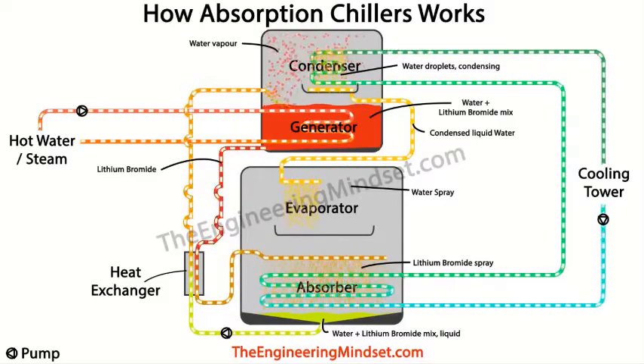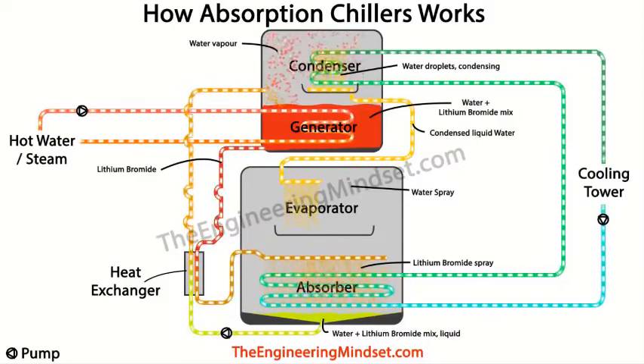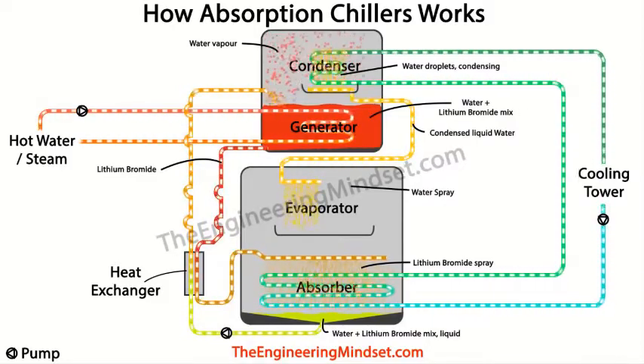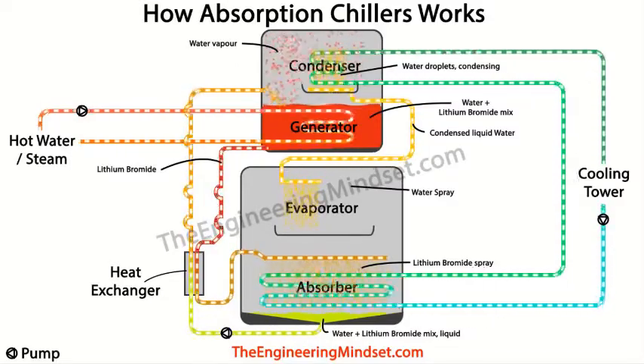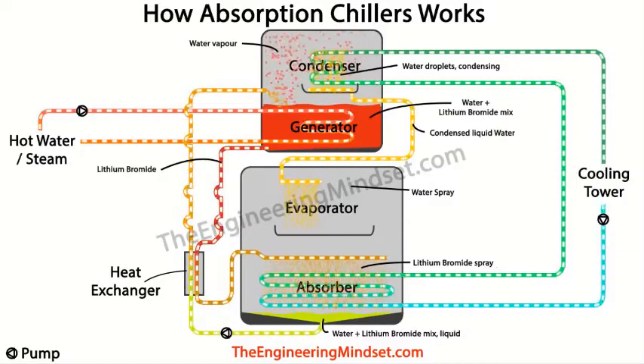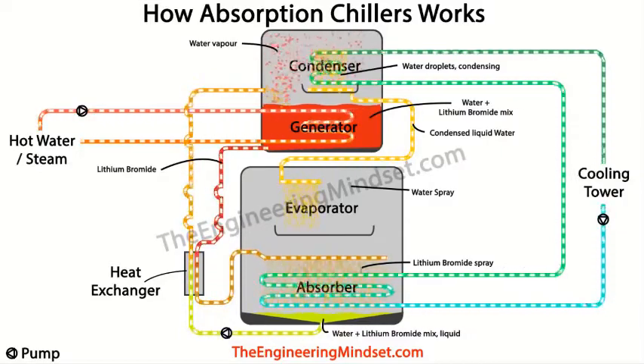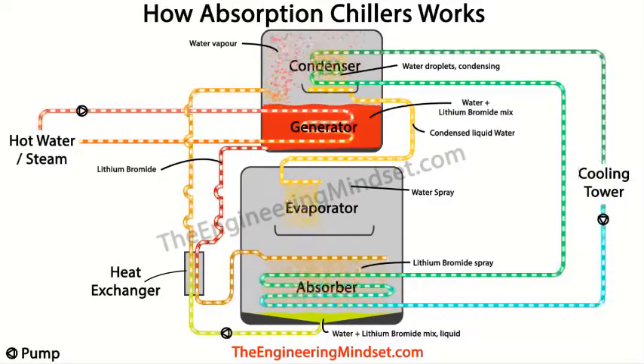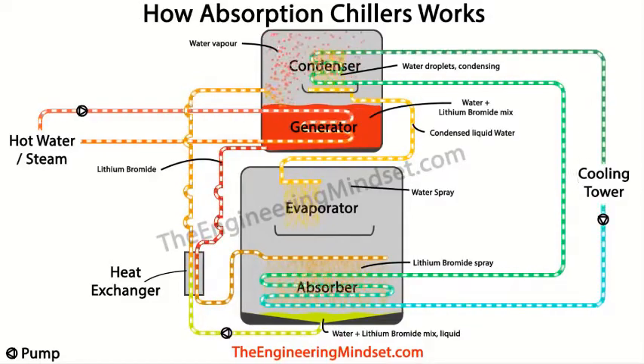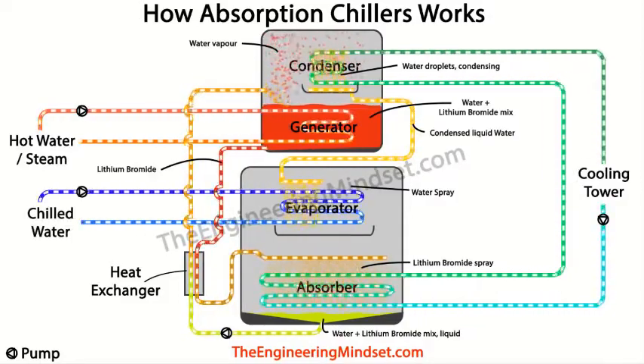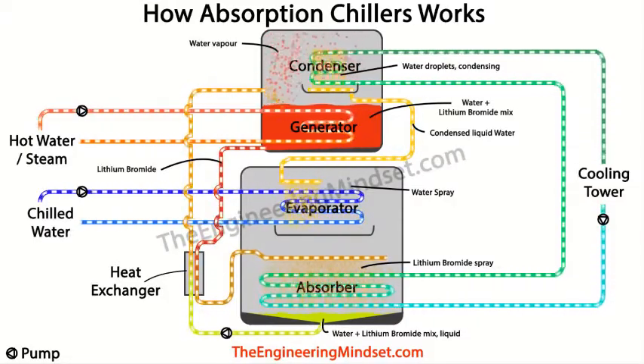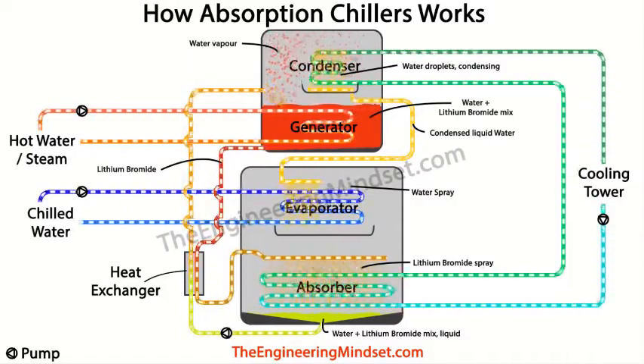Now the evaporator, as we mentioned earlier, is at a very low pressure. It's almost near a vacuum condition. Now this sudden change in pressure will cause that water that's entering to suddenly flash and drop in temperature into a cold water of around just 4 degrees Celsius, maybe 40 degrees Fahrenheit. A chilled water loop then runs into the evaporator, bringing all the unwanted heat from the building, which was collected from the AHUs and the fan coil units, etc.